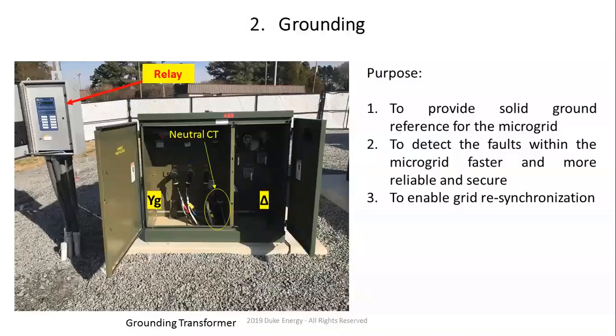Second of all, to detect the faults, with this grounding transformer you can detect about 95% of the faults. Why? Because line to ground faults are the faults that you can detect with this. You cannot detect line to line and three line to ground faults, right? And also, a lot of stuff that you probably do not see during the simulation. This is probably the most critical part. You might not be able to see that you cannot resynchronize to the grid without this grounding transformer.